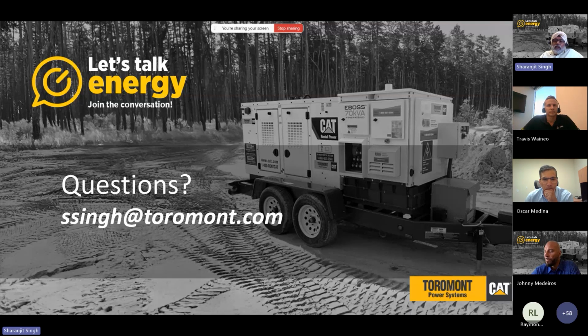One needs to understand what the loads are. The more the load fluctuates, going from high to low, the greater the possibility of using a hybrid system, compared to a steady load, which is more of a generator set application. Am I correct there? Yeah, if you're running something at a consistent 80% load on a standard generator, it's probably a really good application as far as efficiency goes. But if there are a lot of variable loads, hybrid can definitely help reduce a lot of your operational costs.